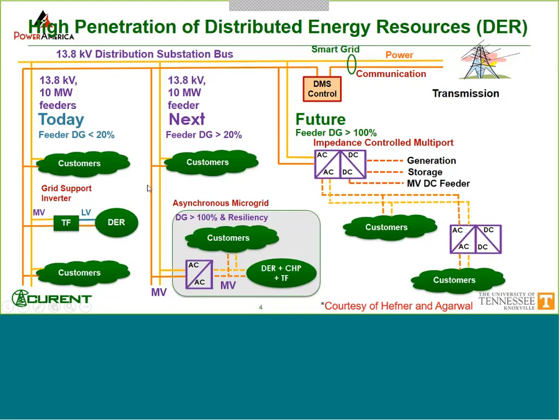That is what we are doing, but in order to increase the penetration of DG, you would have to design it in such a way that both the distribution grid and the DG themselves are designed together to avoid issues like power quality and stability. The next step that will facilitate such a design would be using some kind of asynchronous microgrid, which simply provides an AC-AC link that will decouple the DG or DER from the medium voltage distribution grid, to make the penetration level design much simpler and better for resiliency, reliability and stability.